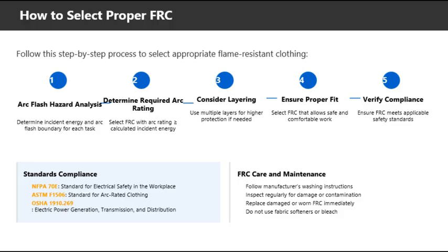Step 2. Determine the required arc rating. Based on the incident energy calculated in Step 1, select FRC with an arc rating equal to or greater than the calculated value. Never select FRC with a lower arc rating than required, it won't provide adequate protection. Step 3. Consider layering. If higher arc ratings are needed than what's available in a single garment, consider layering multiple FRC items appropriately. Remember, all layers must be flame resistant.